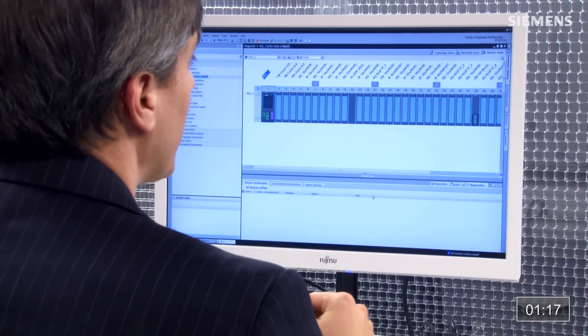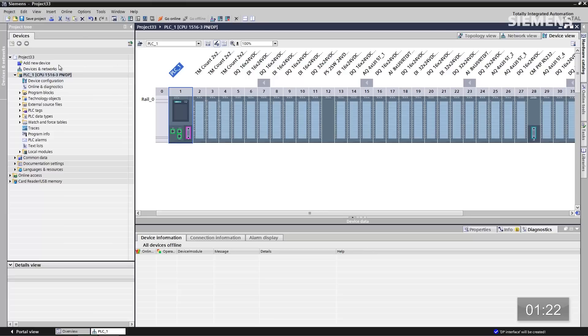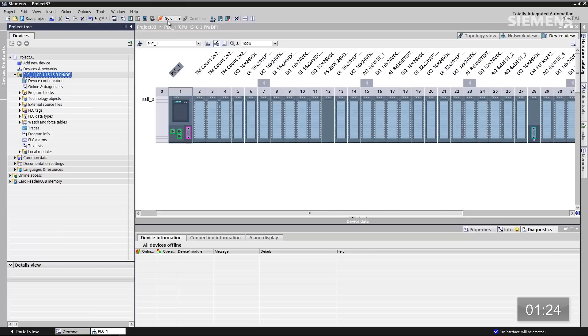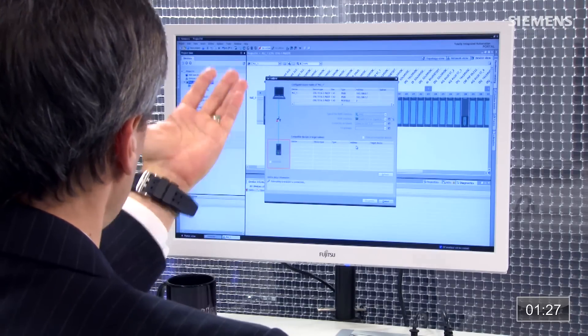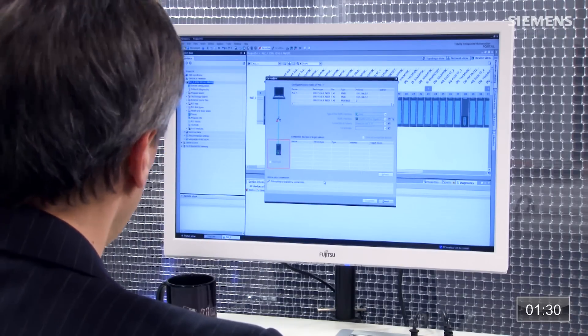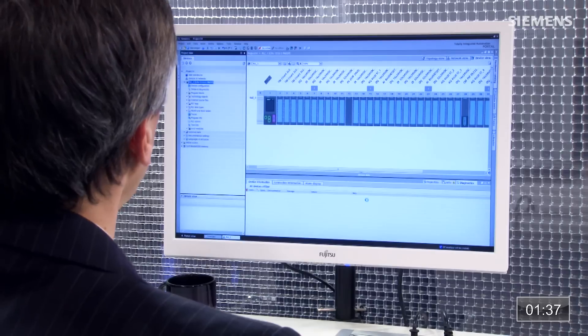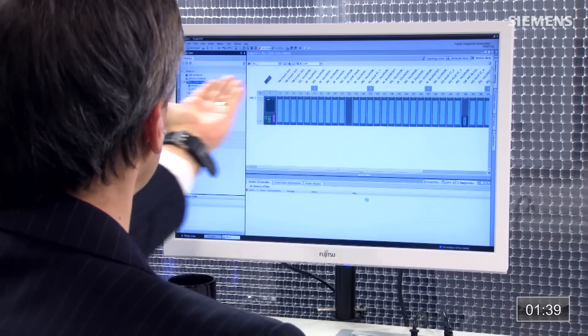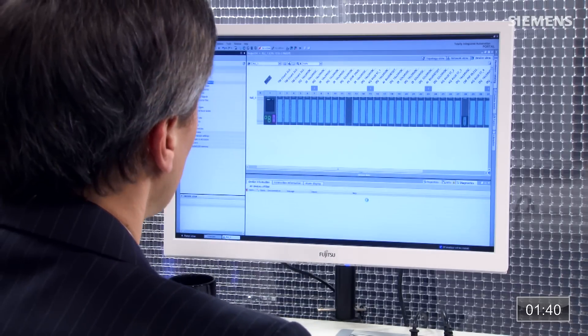Now that I physically have the rack, my hardware configuration is done. For the software, I need to go back and give focus to the actual CPU and click Go Online. It will go out and populate another pop-up box, searching for it right now. Once it physically finds that IP address and device name, I can click Go Online. The way I'll know I'm online is I'll have these orange bars across the top of the software.